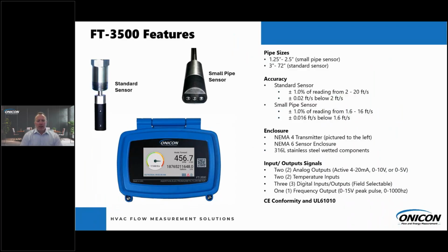Yeah, thank you, Mike. So we want to talk about the features of the FT-3500. What's great about the insertion meter is the wide range of pipe sizes that we can accommodate. It's going to be 1.25 inches all the way to 72 inches. Plus, as Mike mentioned, we're able to achieve that accuracy statement of plus or minus 1% of the reading.